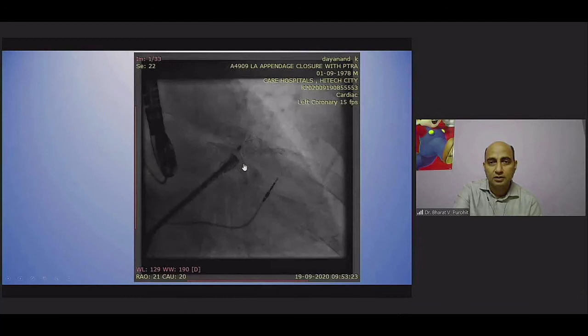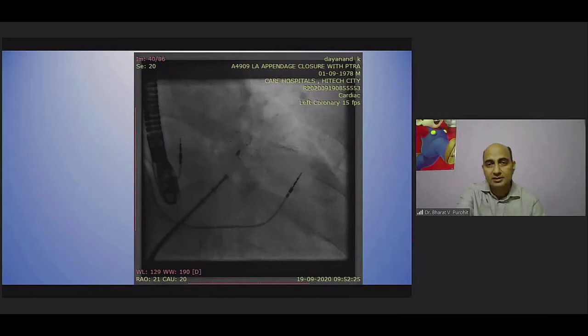And then after realigning, you can see we have pushed the device, and this is how it looks. You can see it has sealed well, and in the TEE also it looked very nice. And we did a tug test. This is how the tug test looked. The device is absolutely properly anchored, and as most of the speakers have told, there is hardly any case report where the Lambre has actually dislodged. So after this, we deployed the device, and the hooks were released, and we did a check shot.